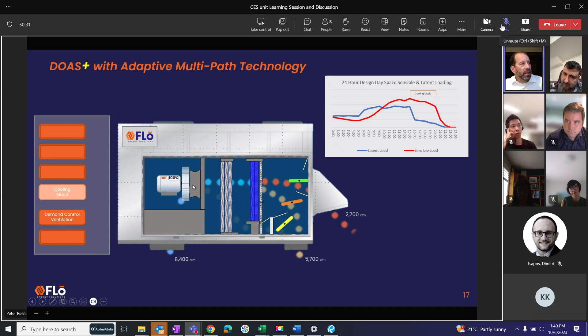The one time that we can change our outside air volume, and again, we need to arrange that with you, is if you want demand control ventilation. So if there's an opportunity because the store is not occupied by a lot of people and the CO2 levels in the air go down, then we have the option, of course, of putting DCV in place, and that will close down our outside damper by up to 10%, and that'll reduce the outside air. Now, that's something we need to work out with you in advance because we need to make sure, of course, that we never go below your exhaust volume of air that you need as well for your seafood and all these other kinds of things. But that's an option there. And of course, that saves energy.